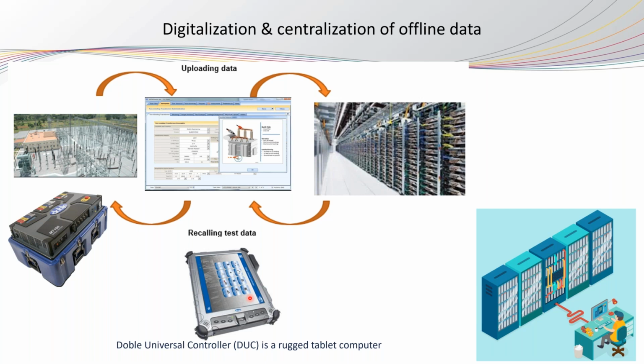And in the end, they will be able to have the same test file again, and they will go to the same transformer. They will not put in the nameplate data or anything. They will just do the new offline testing and again re-upload the test file. With this closed loop, there is a very low possibility of any kind of human mistake in the data entry. And of course, it will allow a centralized database for the offline testing.